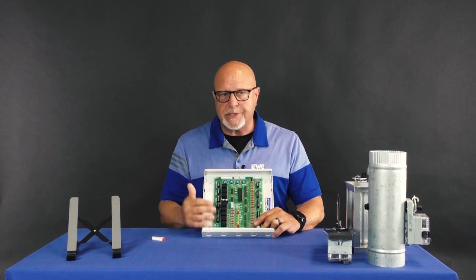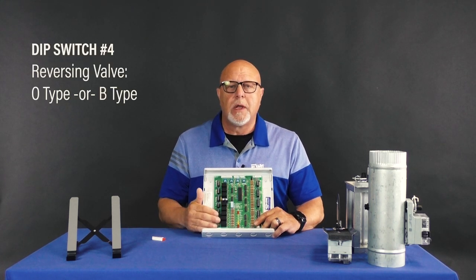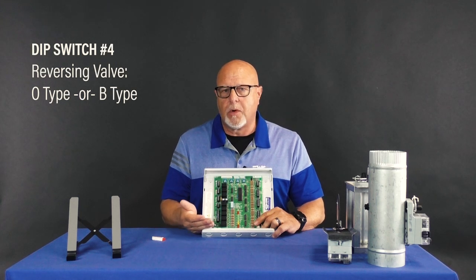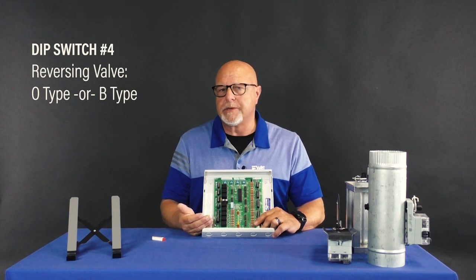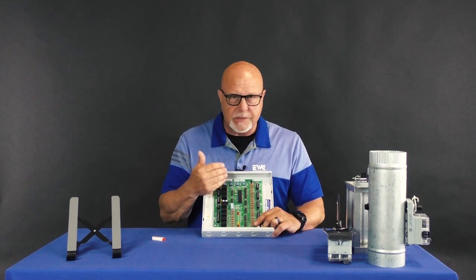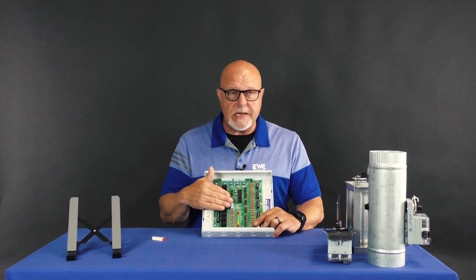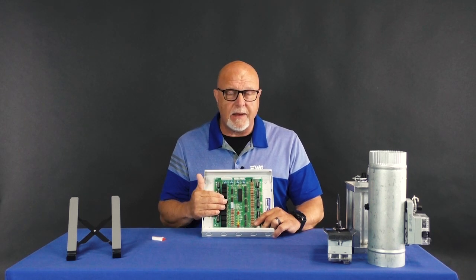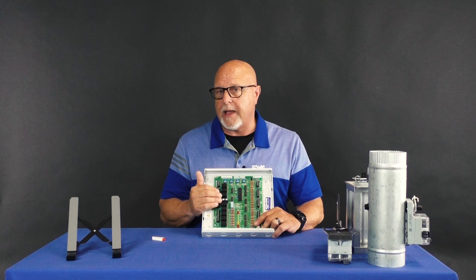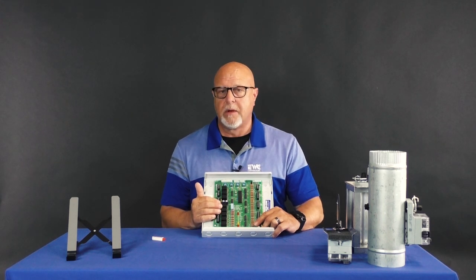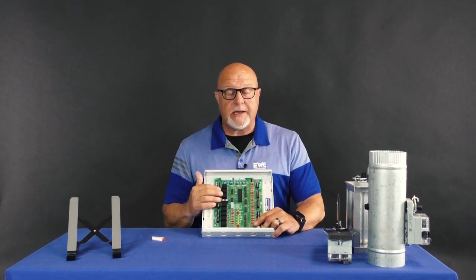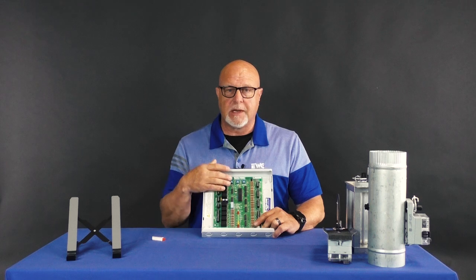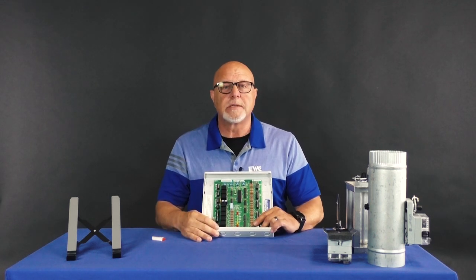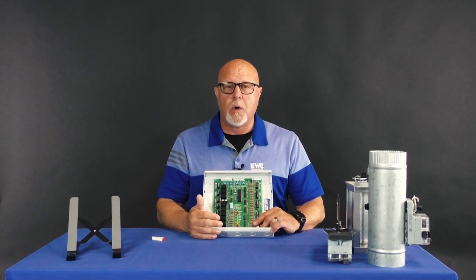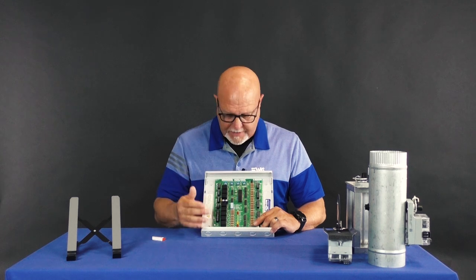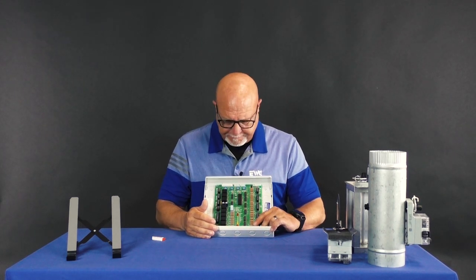The fourth dip switch is telling the board, am I an O-type or am I a B-type reversing valve? So if it's a heat pump, you're going to need to select that. It comes out of the factory as an O-type reversing valve. That dip switch means nothing if you selected a gas type furnace. Obviously, there's no O-type or B-type reversing valve in that type of system.